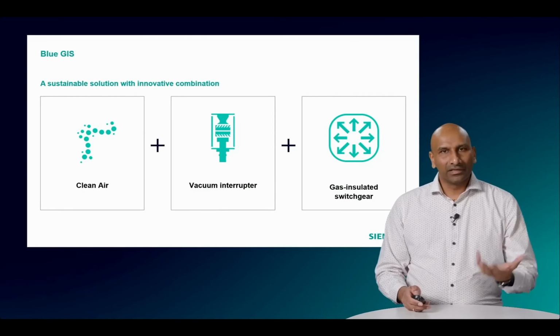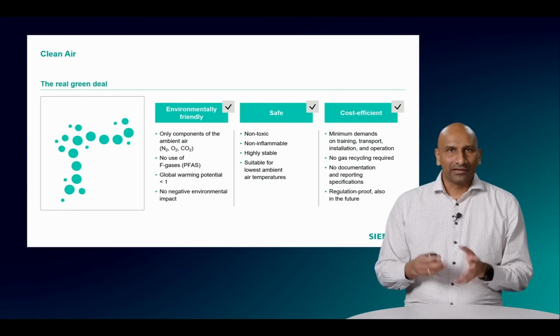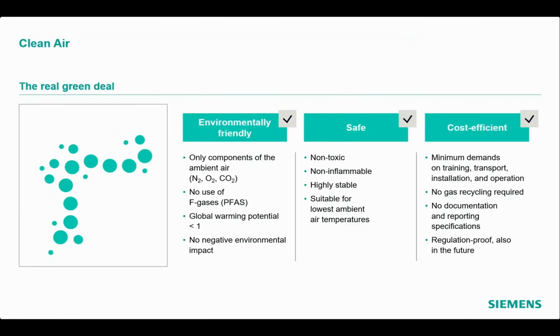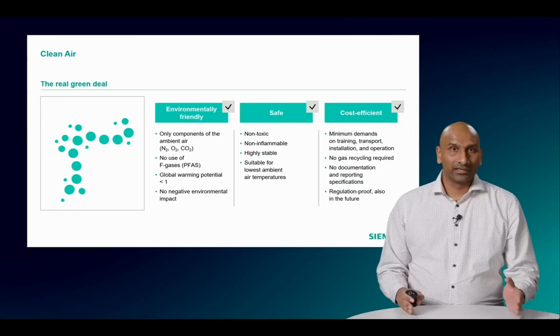The clean air insulation medium used in BlueGIS consists of natural origin gases like nitrogen, oxygen, and carbon dioxide, with a global warming potential of less than 1. It contains no F-gases, making it very safe to operate and enabling easy handling during the lifetime of the switchgear. This insulating medium requires no regulatory instructions, documentation, or reporting.